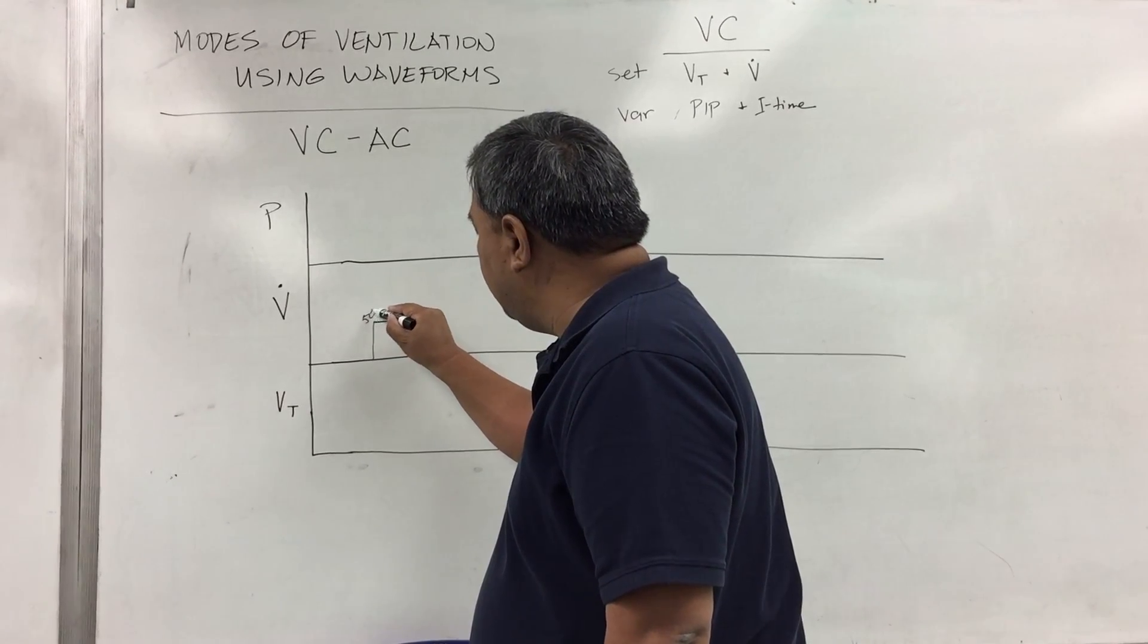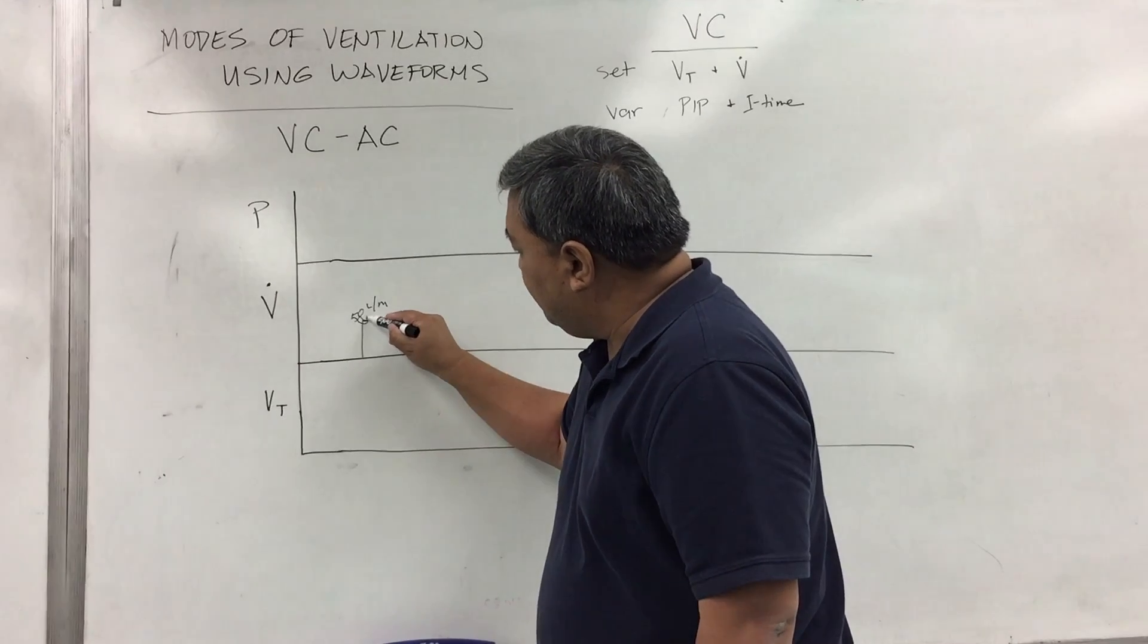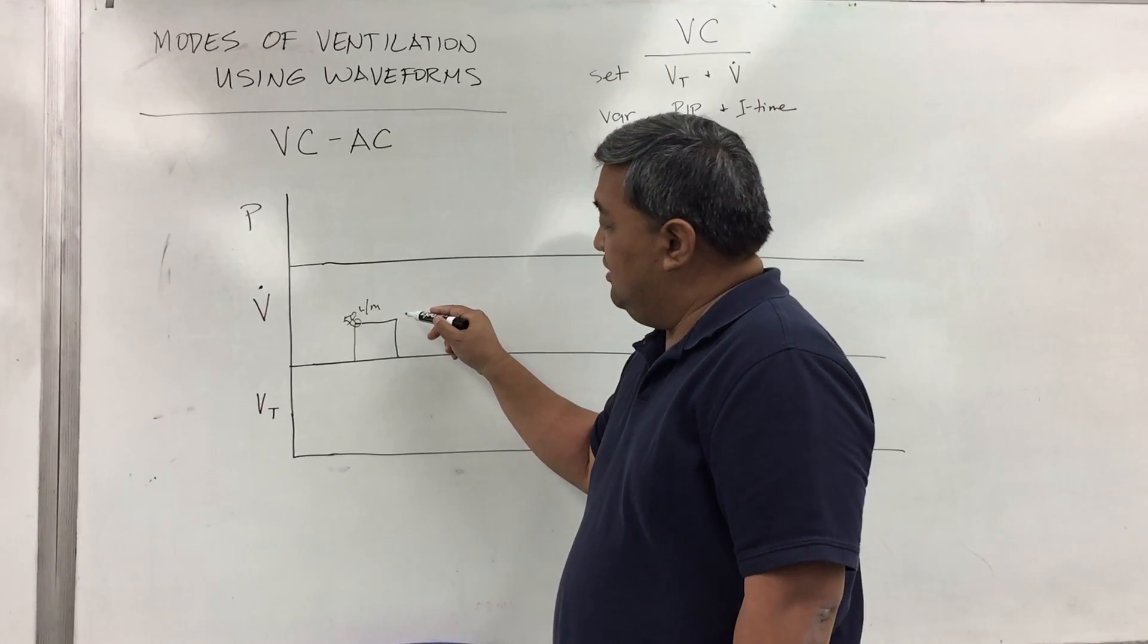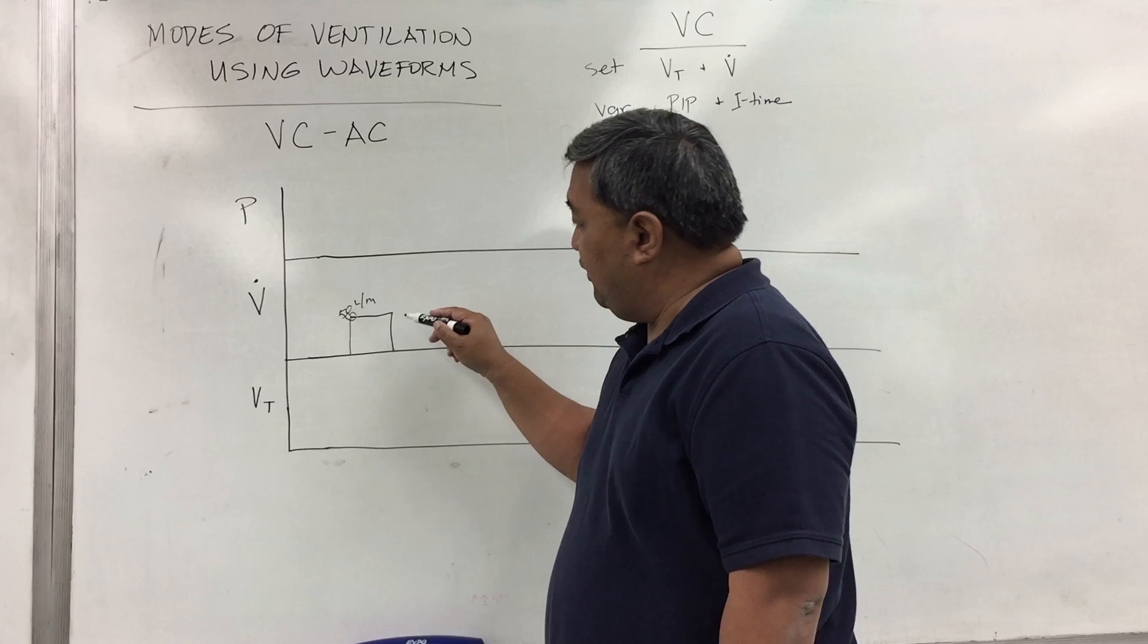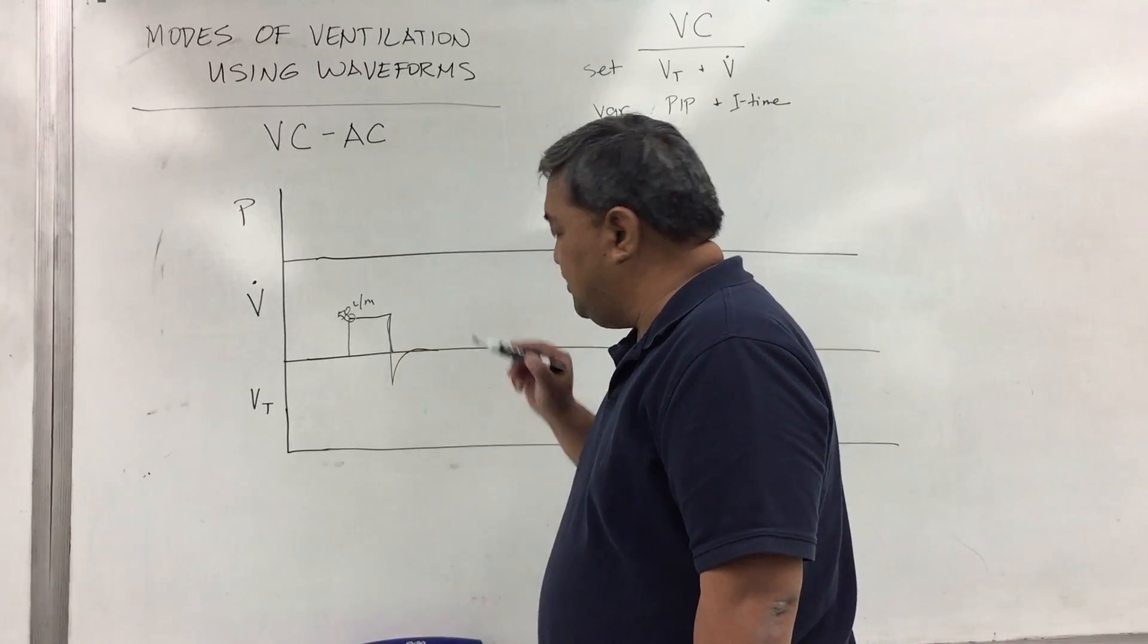So let's say this is 50 liters per minute. That 50 is hit right here. You've achieved that 50 and it's maintaining it. This area here is your inspiration and then from here downward is your exhalation.